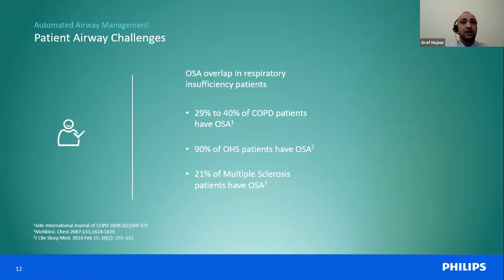So in this situation, if you use the AVAPS feature, you will guarantee the tidal volume of the patient, but you still need something to maintain the patient's airway open. So that's why we added the feature which is automated airway management, and it can monitor the upper airway of the patient. Whenever the device feels that there is a closure or airway obstruction, the device will start to increase the EPAP within a range you put for the patient.